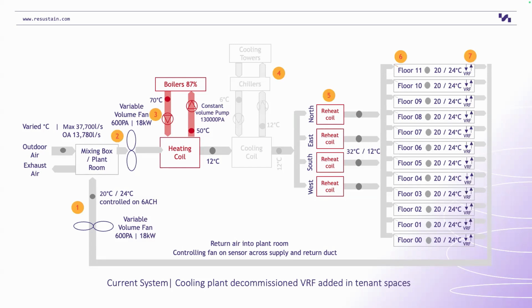So what we found, we have various points on the graph. You've got your return air temperature and your return air fan. We found that there was quite a lot of air going back into the mixing box, as it were, the plant room. And the temperatures were higher than maybe we thought, slightly higher than 24, 26, sometimes 27. And then you've got your fresh air coming in. They needed 13,780 litres for removing the CO2 from the building for the occupants. It was designed for 37, but I think it was actually coming through at around 25, 26. So a lot of air coming in that was mixed.